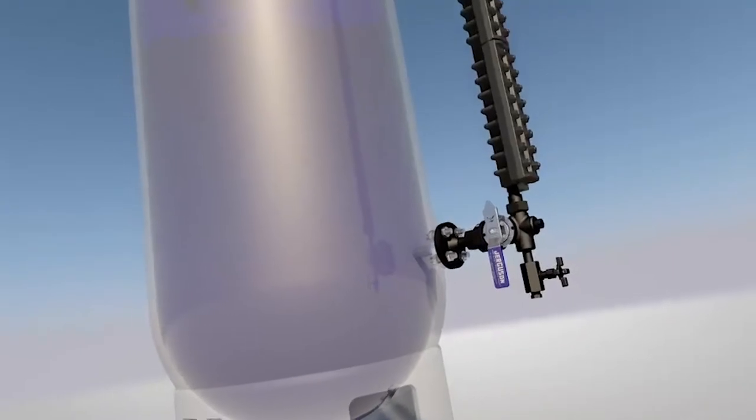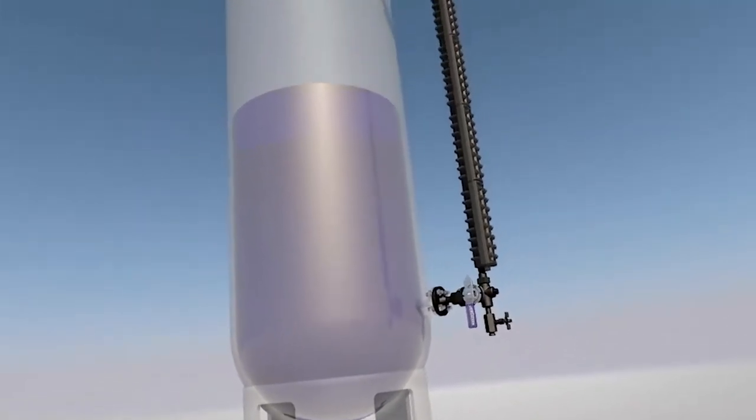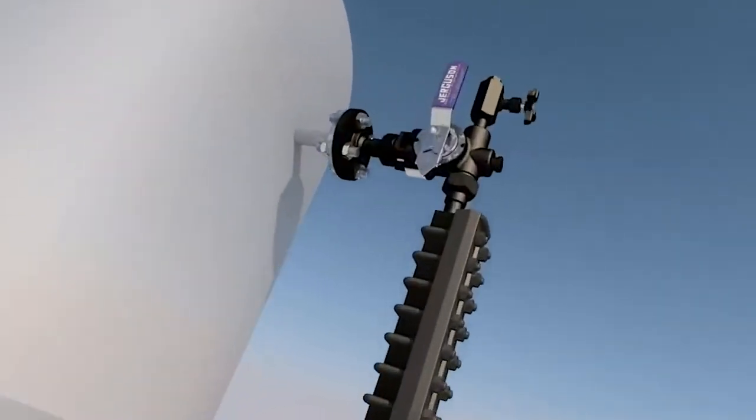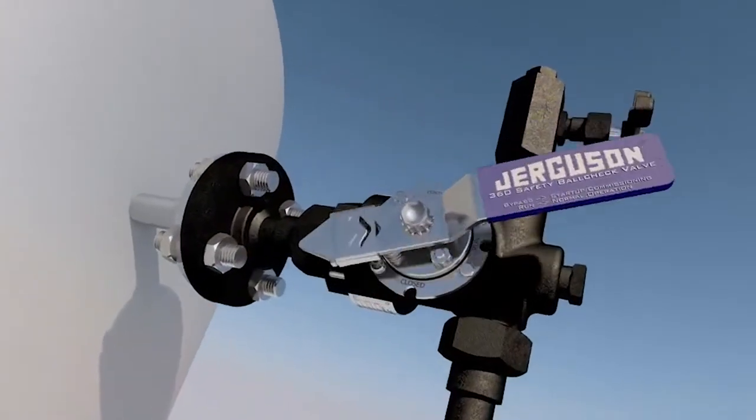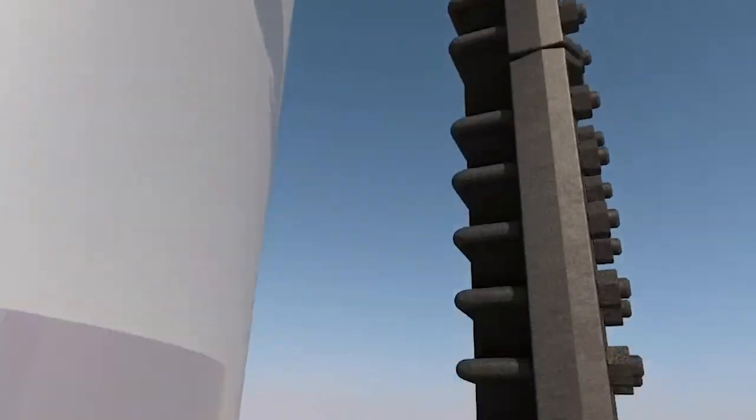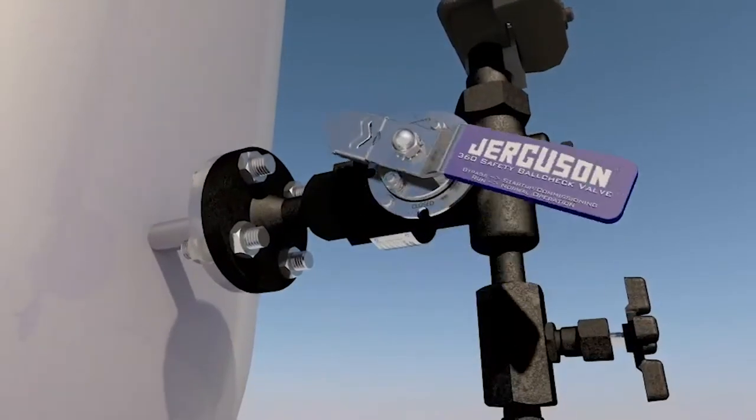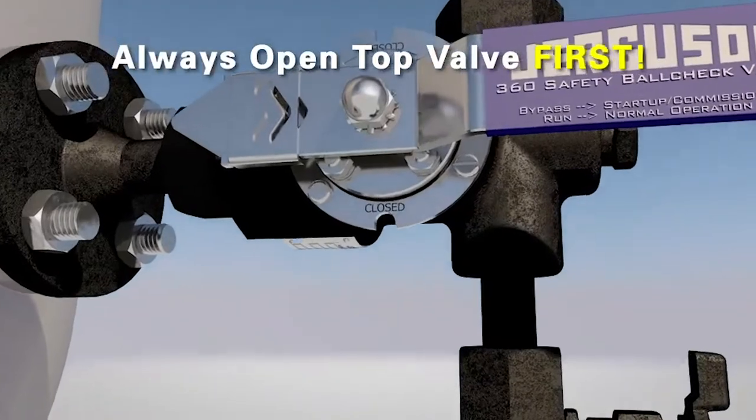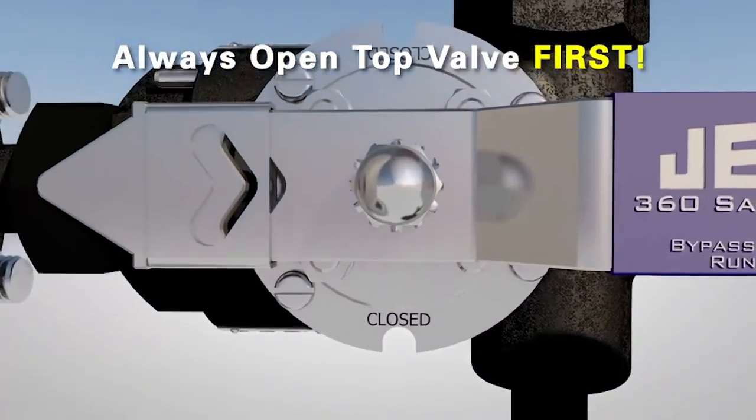The commissioning procedure is quite simple compared to traditional glass gauge ball check valves. When there is already liquid present in the vessel, open the top valve to the bypass position, then the bottom valve. It is best practice to always open the top valve first when commissioning any level device.